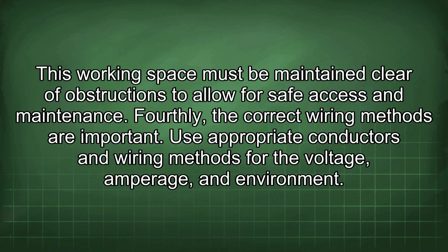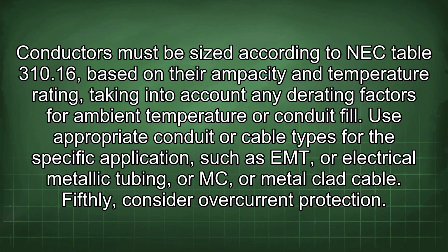Fourthly, the correct wiring methods are important. Use appropriate conductors and wiring methods for the voltage, amperage, and environment. Conductors must be sized according to NEC Table 310.16, based on their ampacity and temperature rating, taking into account any derating factors for ambient temperature or conduit fill. Use appropriate conduit or cable types for the specific application, such as EMT, or electrical metallic tubing, or MC, or metal clad cable.